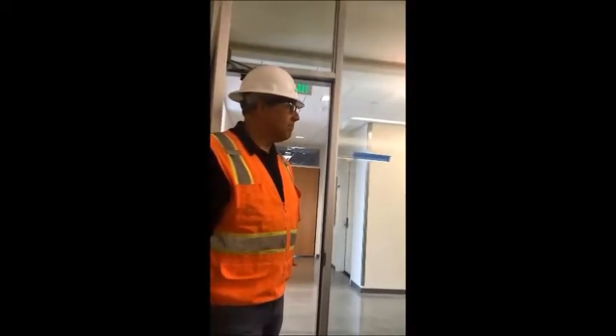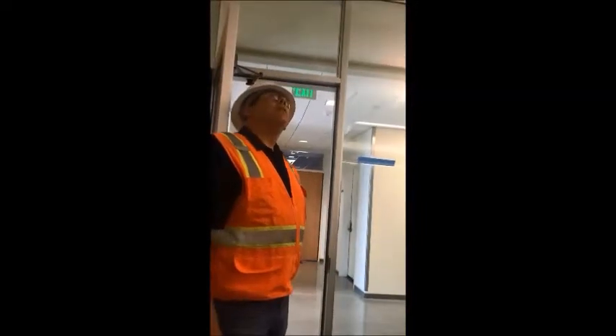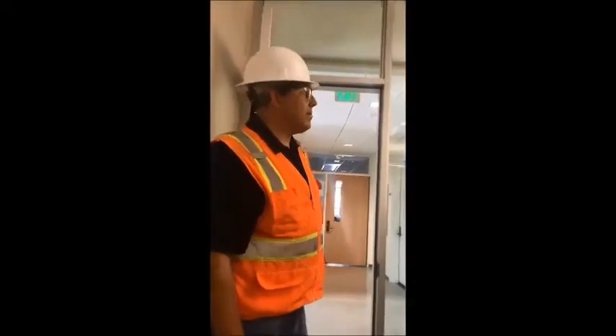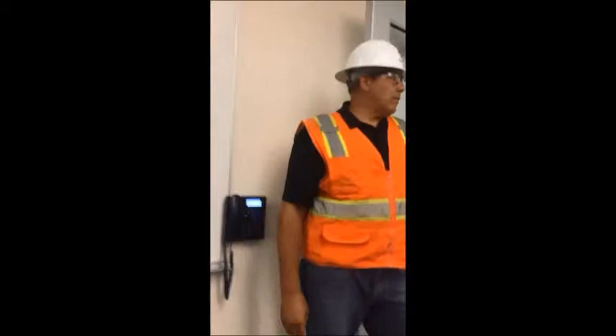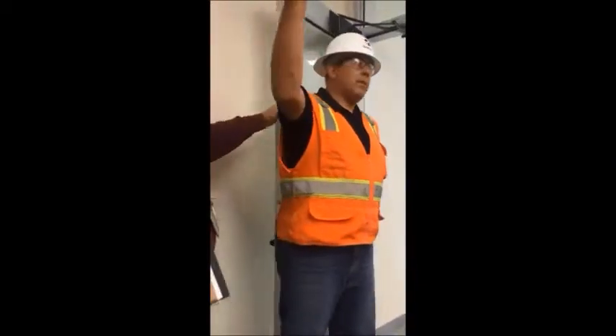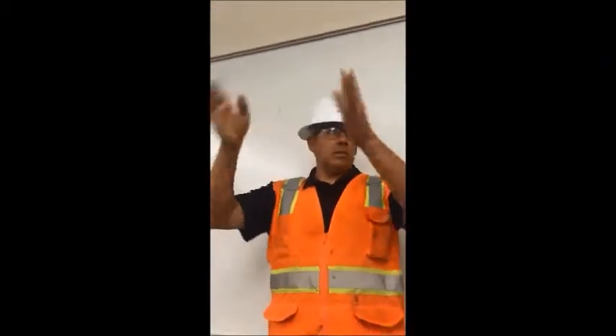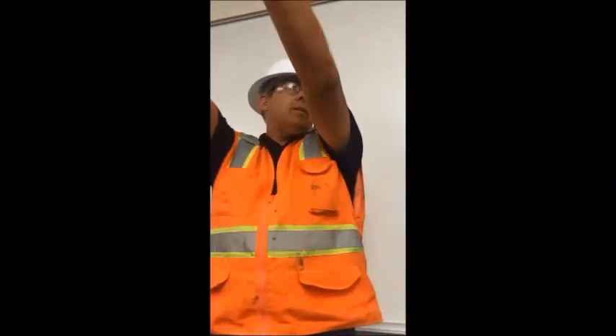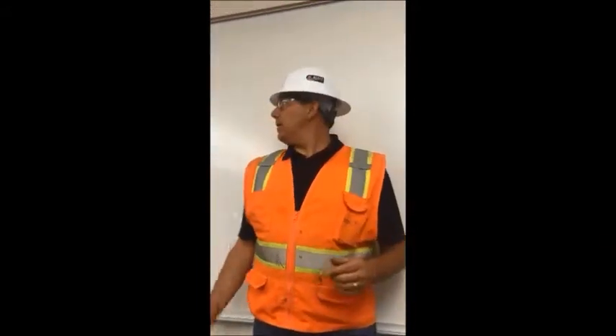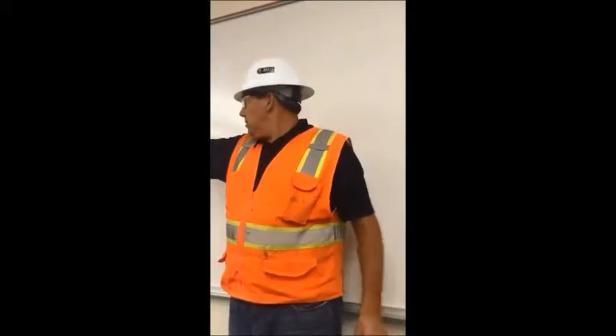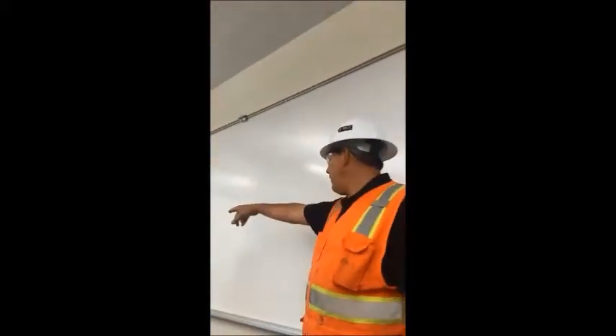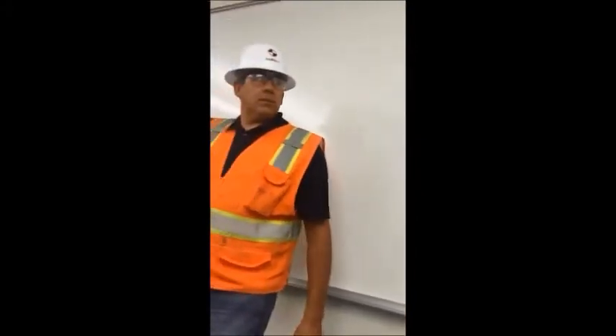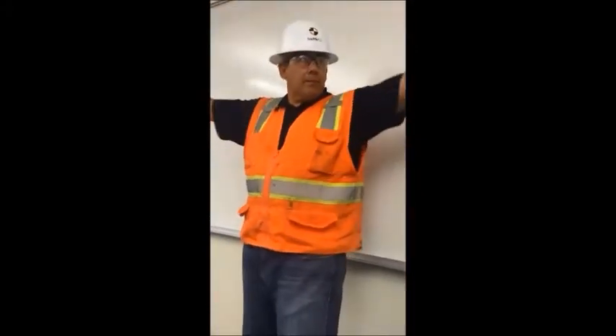Are any of the valves or anything marked as far as location? I see this blue dot, is that? Yeah, blue dots, I think it was like CAD access. Okay. We'll take a look. Most of the main valves to do the chill beams, chill water and heating hot water are right above here. So in this interior area, the lines come straight through here and feed the chill beams, as far as heating hot water, off of this room. And then again, the lines branch off, so about 10 feet in from that door, the lines turn left. Again, we have to support the chill beams so they wrap around the extremities.